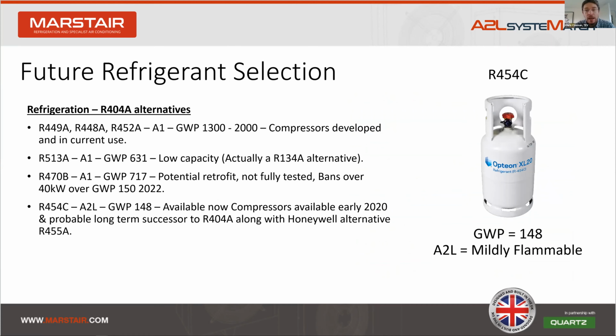So future refrigerant selection. We needed to select a refrigerant to suit the F-gas phase down for 2030 and beyond. We know 448, 449 and 452 are all in current use, but with GWP levels of 1300 or above, something needs to change. R513A is an interesting option. It's not flammable and compressors are coming available, but it's actually a 134A alternative, so its capacity is very low, and ultimately it doesn't get the GWP level down as low as where we need it to be. Other refrigerants like R470, which is also an interesting option, but again, with a GWP of 717, it doesn't get the GWP down low enough.